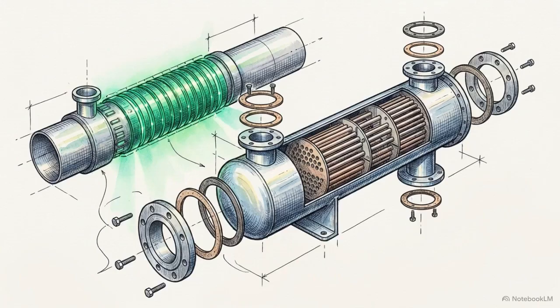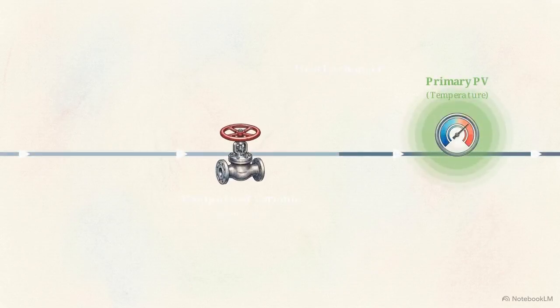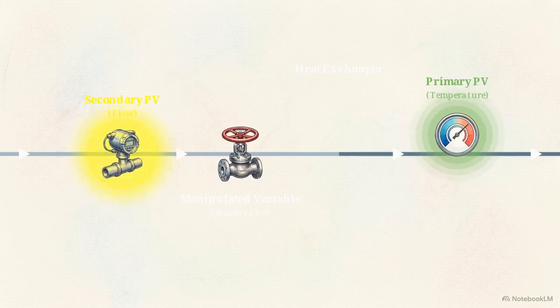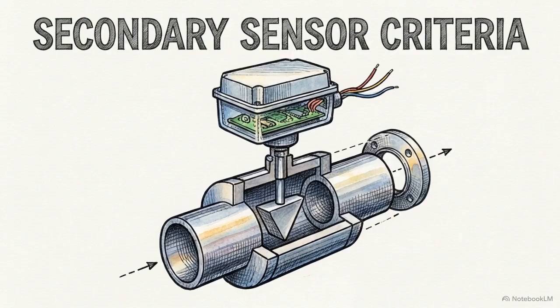To fix this, we need a way to feel that disturbance the moment it arrives, long before it has time to affect the final temperature. We do this by adding a secondary process variable. In this case, we install a flow sensor directly on the steam line, right upstream of our control valve. You can't pick any sensor for this. A valid secondary variable has to follow strict rules.